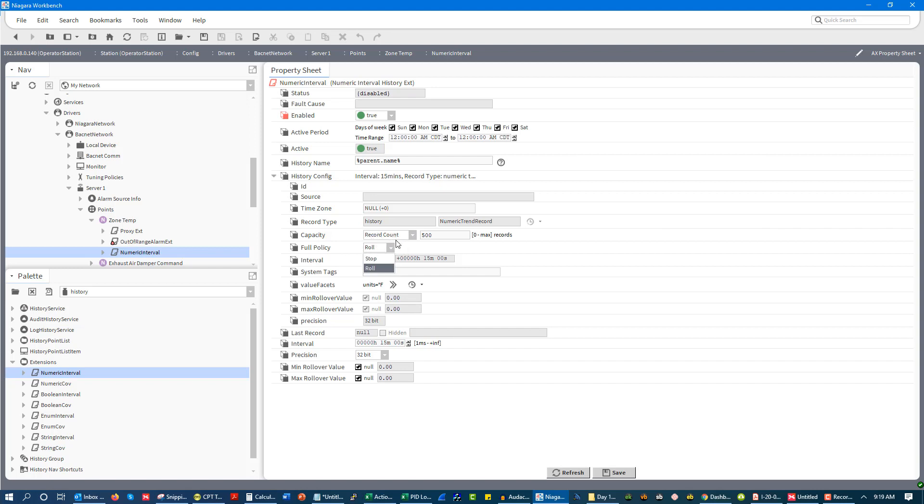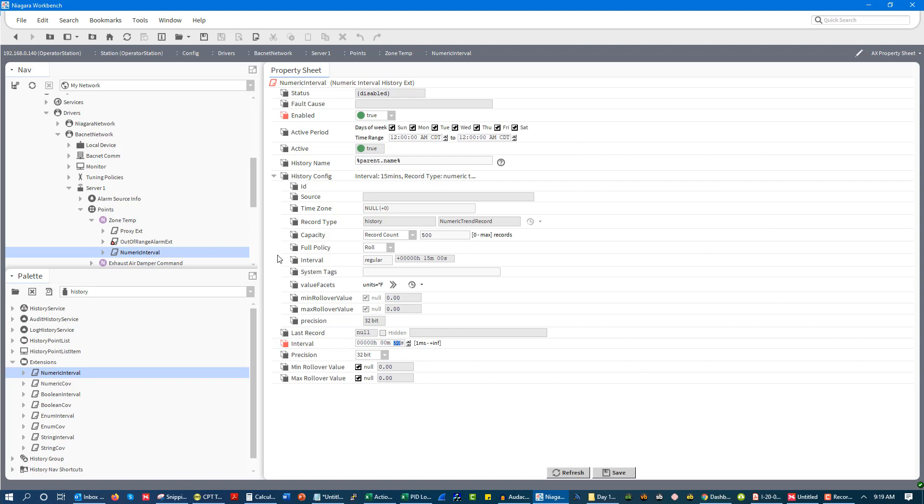Do I have a capacity by record count? What's my policy when my record count is exceeded? Do I just roll over or do I stop logging? What's my time interval? How often am I going and trending these? And I can set up a whole slew of things. So if I wanted to, I could go and say, every 30 seconds, I'm trending this. And I could set all that up. And there you go. Once this is all set up, and I'm going to set this up right now.